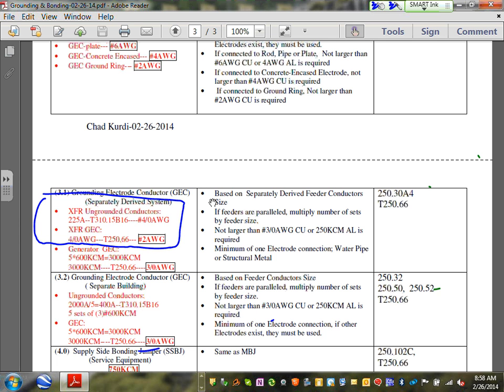Okay, so this is called grounding electrode conductor, guys. How do you size a grounding electrode conductor? Exactly like any others. At the separately derived system, based on the feeders, not larger than, it does not need to go larger than these two numbers, exactly like at the service. You have to tie it to at least one grounding electrode, water pipe or structural steel of a building. If you parallel, you have to multiply the sets, like at the service.